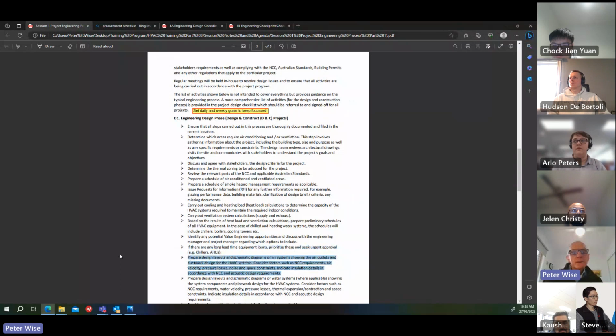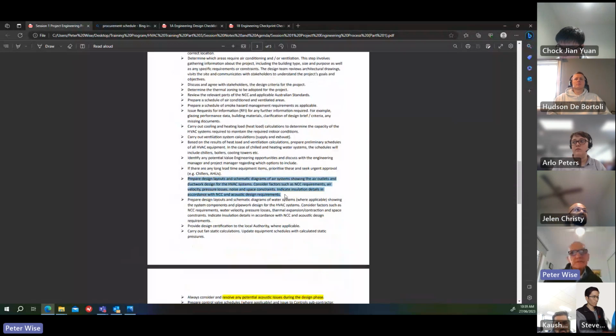Then you can prepare design layouts and schematic diagrams for the air systems, showing air outlets and ductwork design for the HVAC systems. Consider factors such as the NCC requirements, air velocities, pressure losses, noise, and space constraints. Indicate insulation details in accordance with the NCC and acoustic design requirements. All this information needs to be marked up to give to the drafting team so they can continue with their work.